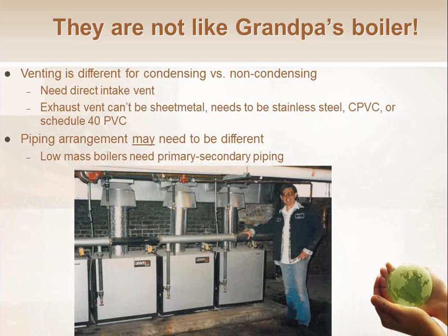You might have to switch to low mass, primary, secondary piping with some of the low mass boilers. We'll talk about some reasons for that in a little bit here. But the basic issue is that I need to have a reasonably high flow through a reasonably tight wound heat exchanger when I go to these low mass boilers. So with an old cast iron boiler, like the ones in this picture, you basically got, I don't know, a 2-inch pipe coming in, dumping water into this big drum, and then pulling water out. The pressure drop is very low.